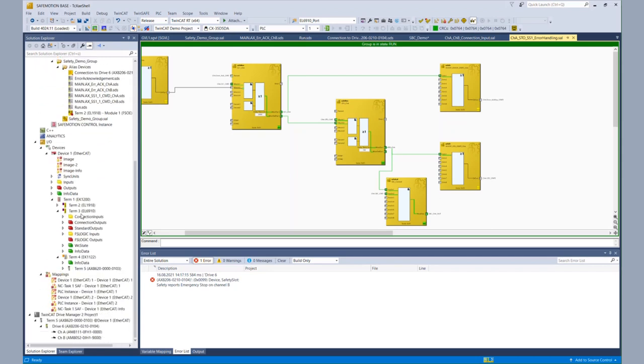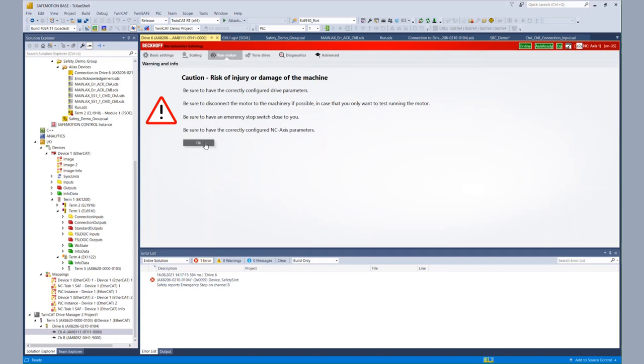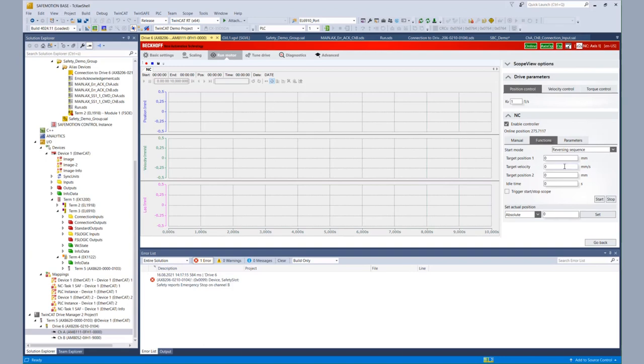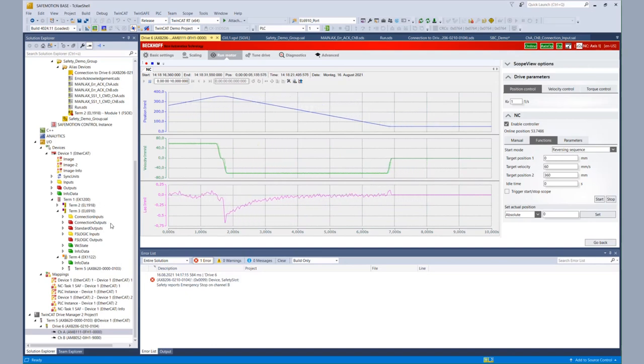So we go to the drive manager of channel A, go to the tab run motor, confirm we are sure, and then configure our motor movement. If everything works correctly, after entering the velocity and the target position, we click on start. There is no error message and we activate the scope. We see that our SBC is working fine — TwinSafe gives the release to the brake based on the STO signal and the SBC command, and we can use the motor as we wish.